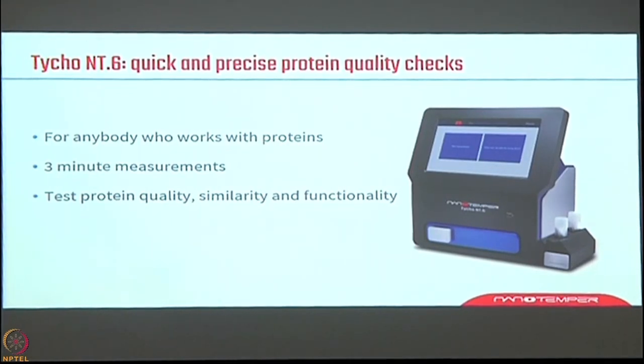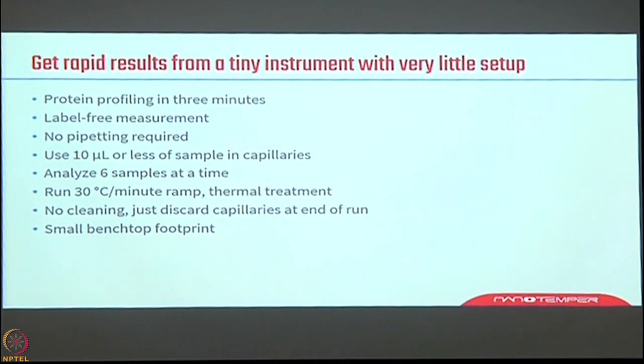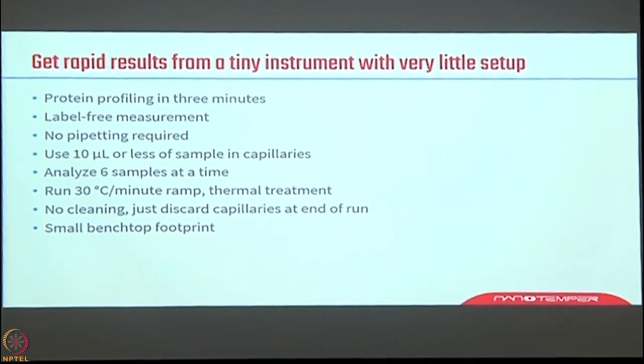The basic principle of this machine is that it can work with any kind of protein — whether it's an antibody, a normal protein, membrane protein, or receptor protein — and gives a three-minute measurement. Within three minutes, you are actually checking the quality and purity of the protein. It is a label-free measurement — not labeling any partner. It checks the intrinsic protein fluorescence, which gives you a label-free inflection temperature very equivalent to the melting temperature.